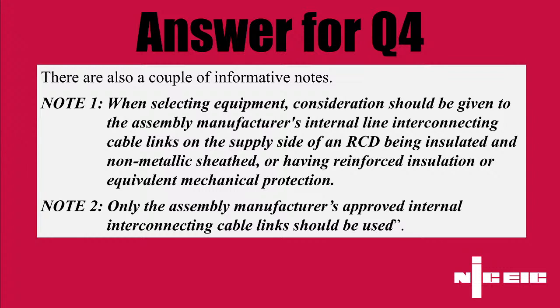So going back to the first part of the question, if it truly were an extraneous conductive part and it hadn't been installed, if you were then doing additions or alterations that relied on the equipotential bonding, and you were using ADS, then you would need to consider adding it if it had been omitted incorrectly in the first place. But the second part of the question leads me to think that it's not an extraneous conductive part if it's a plastic incoming pipe. So if it is not extraneous, then you wouldn't need to bond plastic pipe.